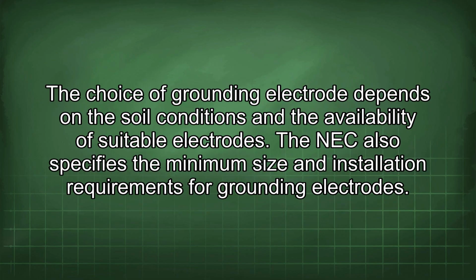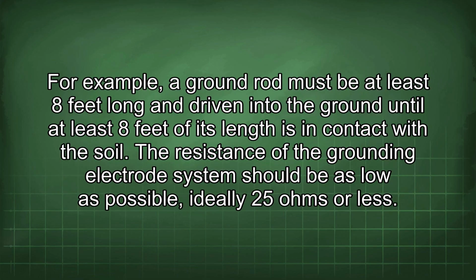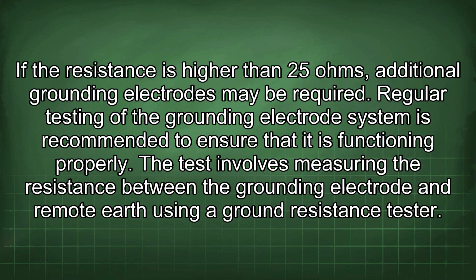The choice of grounding electrode depends on the soil conditions and the availability of suitable electrodes. The NEC also specifies the minimum size and installation requirements for grounding electrodes. For example, the ground rod must be at least 8 feet long and driven into the ground until at least 8 feet of its length is in contact with the soil. The resistance of the grounding electrode system should be as low as possible, ideally 25 ohms or less. If the resistance is higher than 25 ohms, additional grounding electrodes may be required.